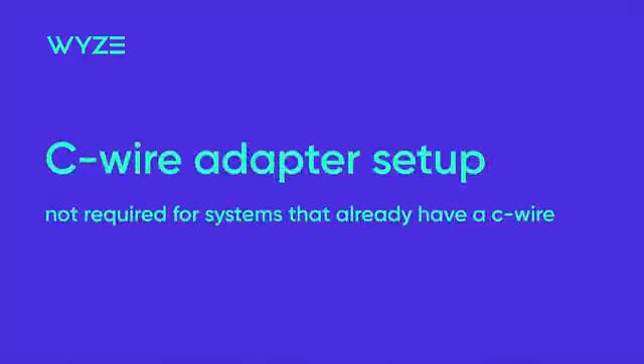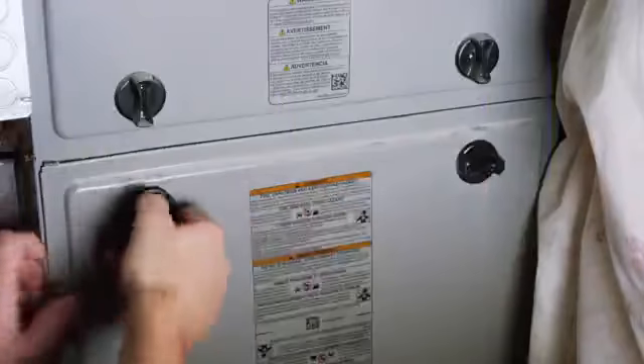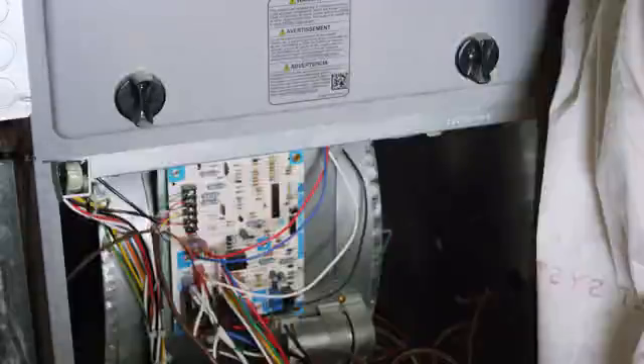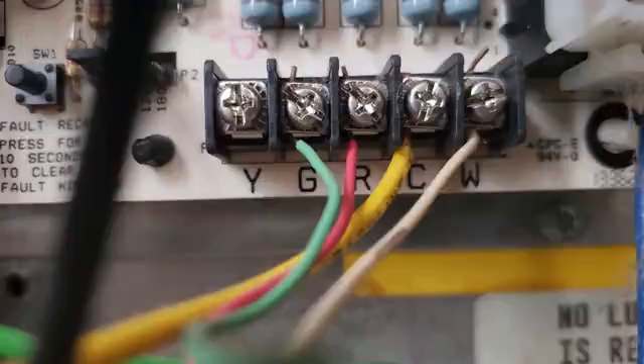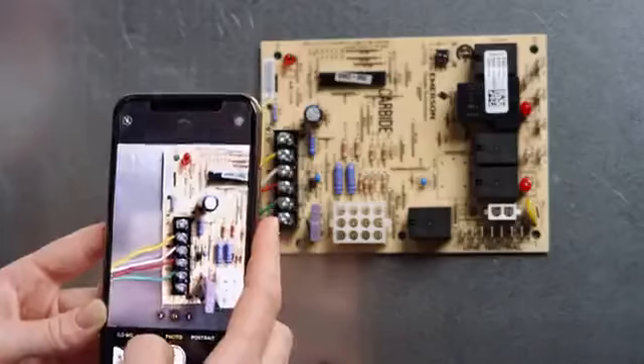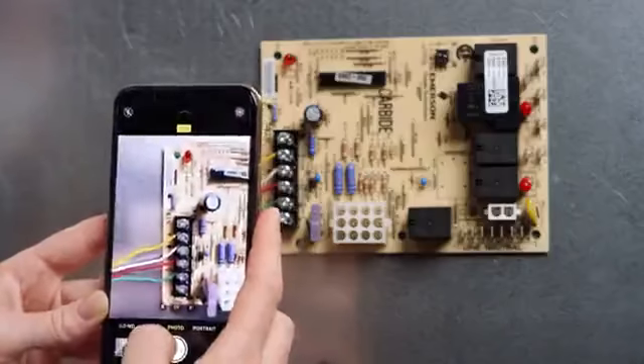Wyze thermostat comes with an optional C-wire adapter for systems that don't have a C-wire. Installing the C-wire adapter is easy. To start, open your HVAC system cover to expose the control board. Some systems may have two covers you need to remove. You will know you've made it to the control board when you can see wires connecting to the terminals labeled Y, W, G, and R.